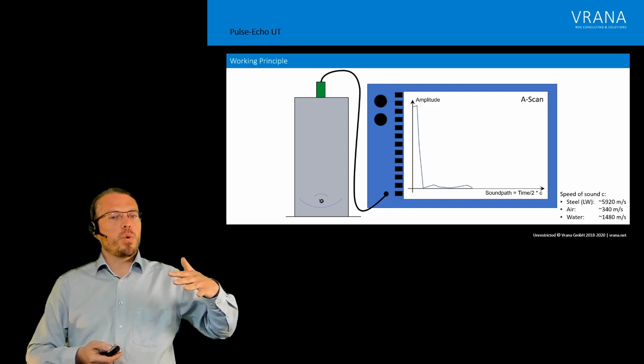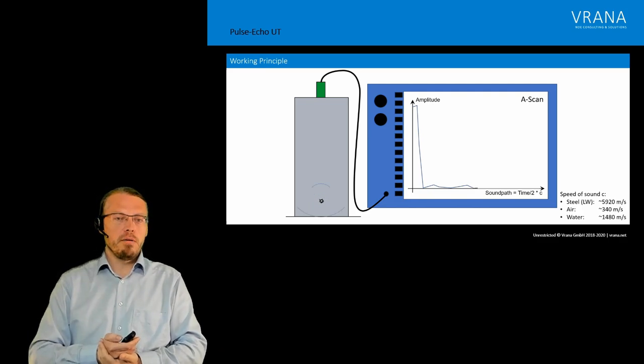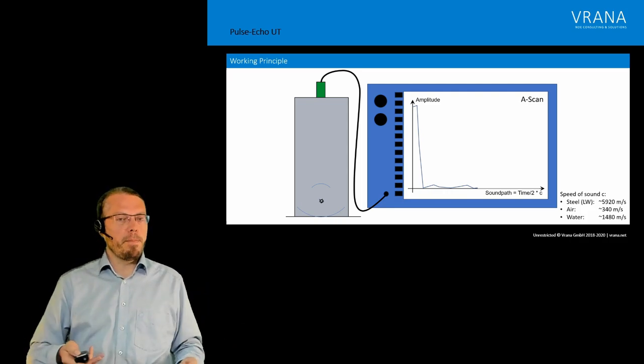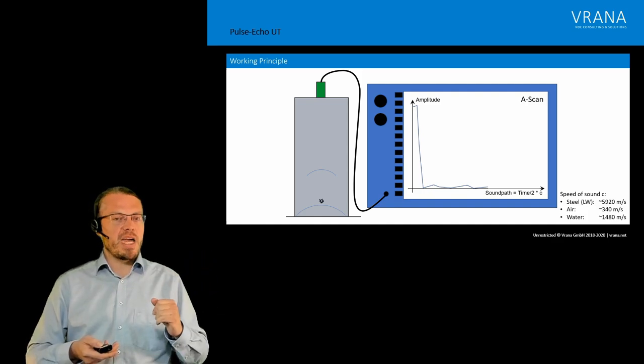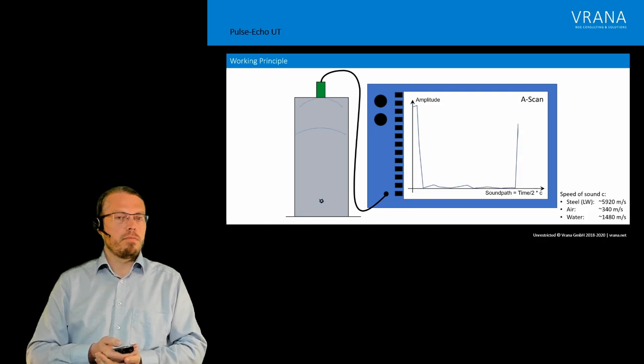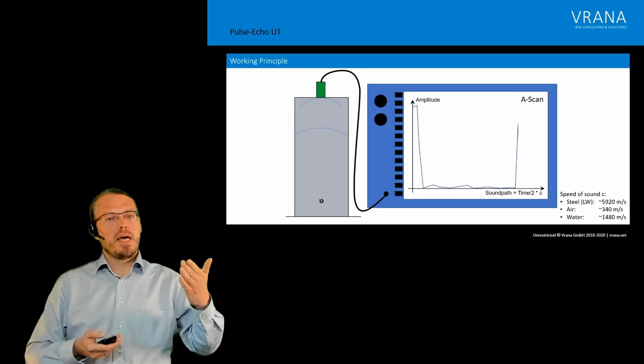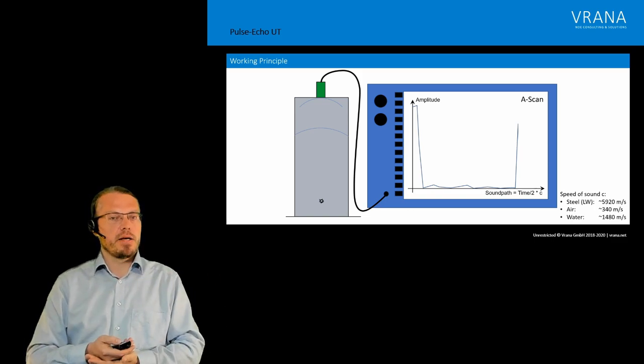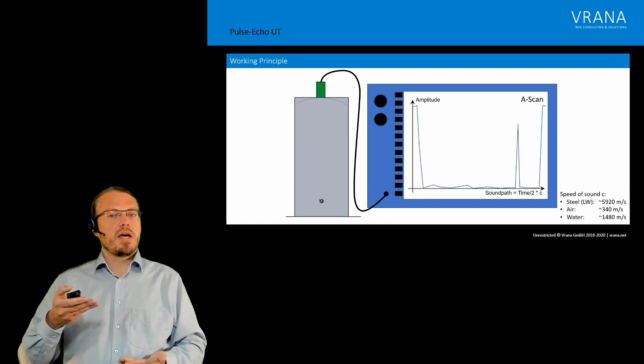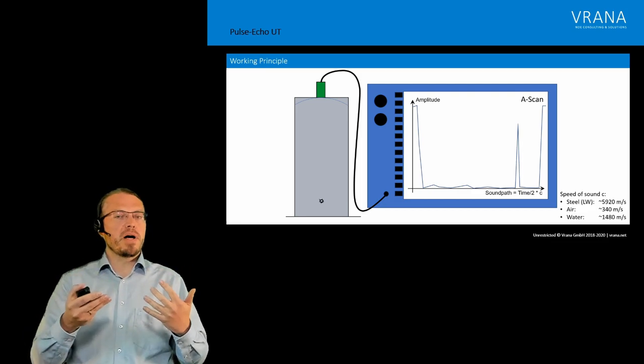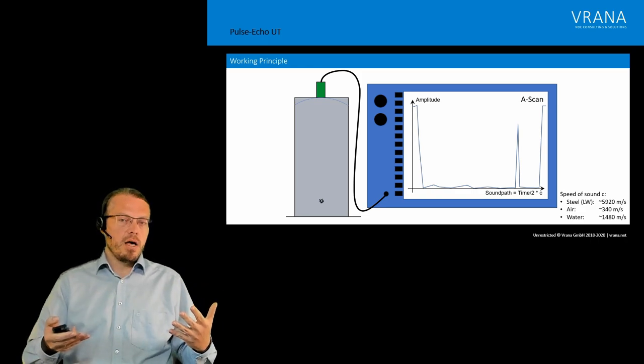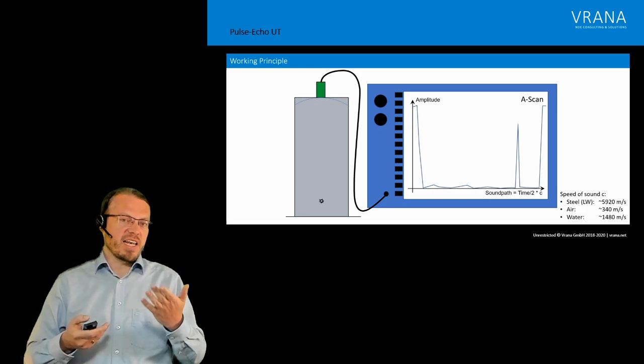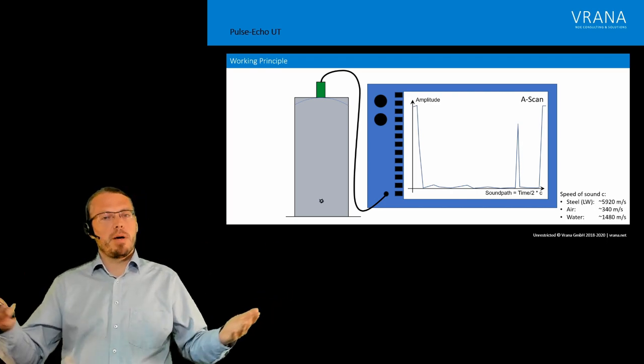But it also has to travel back from the indication back to the surface so that we can see it. All what we have seen up to the moment of the A-scan is actually the dead zone in the beginning and then some noise from the first half of our component. Now we are getting into a wave which is reflected back from our defect but another one which is traveling further to the back wall. Now we are hitting the back wall and that wave gets reflected also on our back wall. So now we have two waves coming back, one from our indication and one from the back wall. Now our first wave actually hits our probe and now we are seeing the signal on our A-scan. And a couple of hundred nanoseconds later we also see a signal from the back wall. This is a typical screen you see on a pulse echo A-scan. You can see something like that. That's typical signal of an indication. You see the dead zone and you see a back wall.